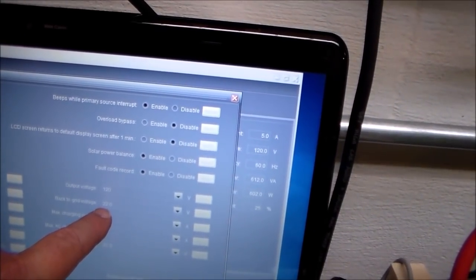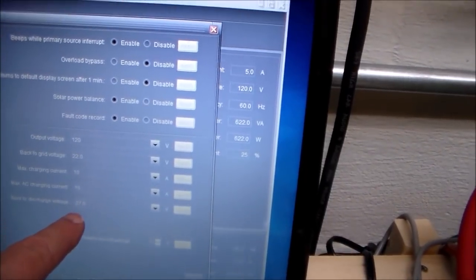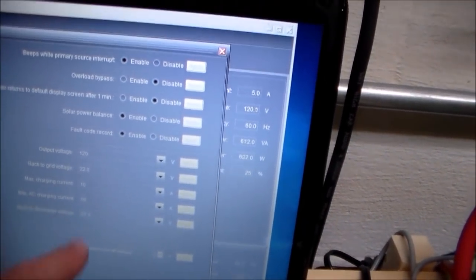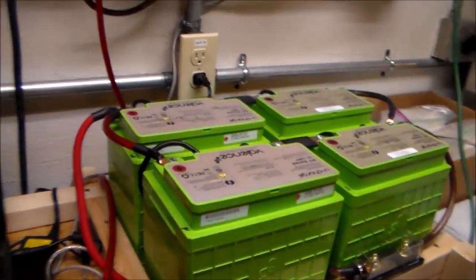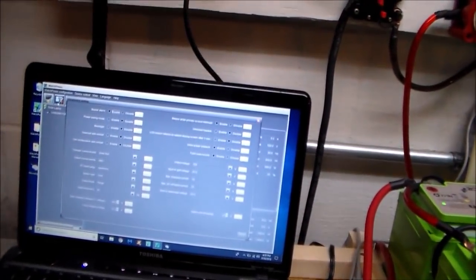I've got my maximum charging current set at 10 amps for solar, and the same 10 amps for AC charging. Once it's charging, this is the cutoff voltage — it'll switch back to the grid at 22 volts. This number means that when it hits 27 volts, it'll automatically switch back over to using the batteries. So that's what I've got going on now for this system.